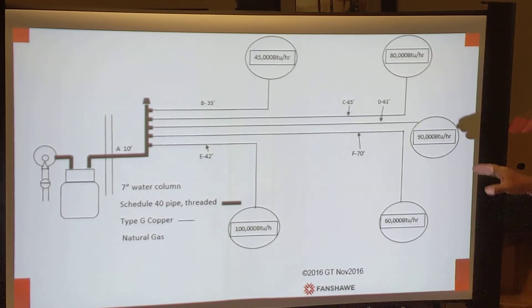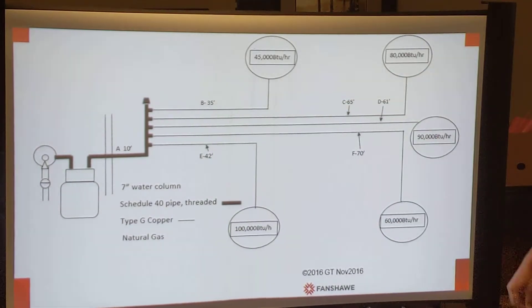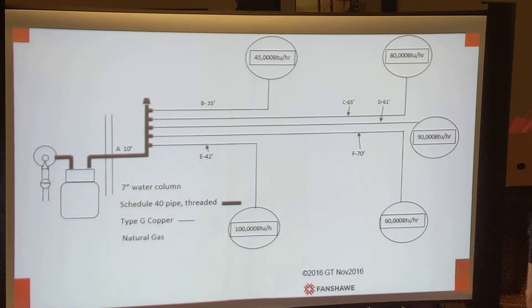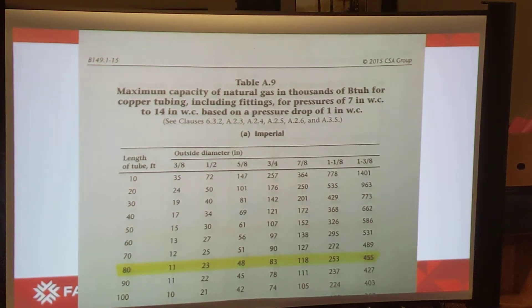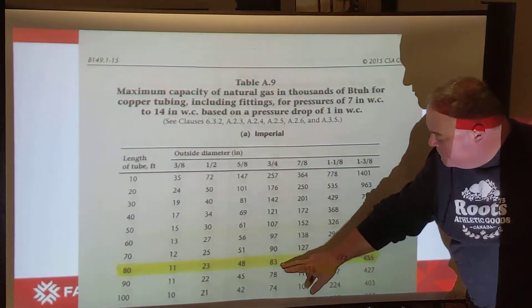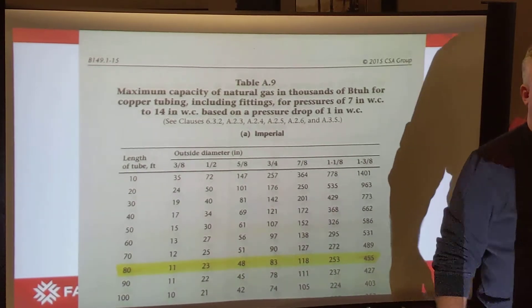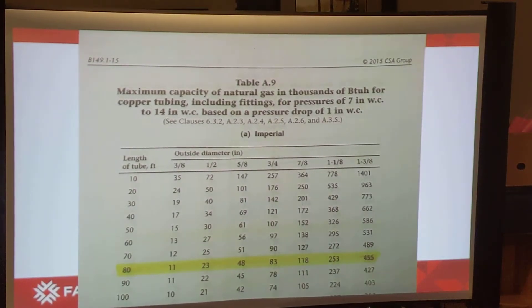For section D, we have 61 feet plus the original 10 feet, so our actual pipe run is 71 feet. We go to the 80-foot code zone with an appliance of 90,000 BTUs per hour. Running across the table to find a number of 90 or higher, we see 118 — so 7/8-inch tubing is used for that particular run.